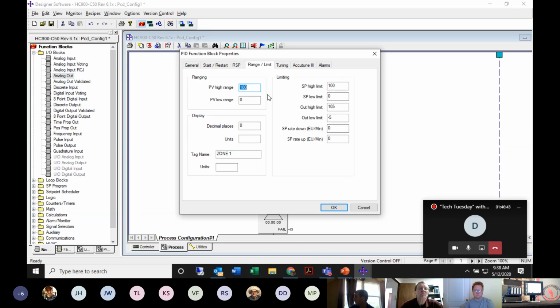Range limits, again, these are the same things you see in a UDC when you program it. You're asked for your PV high range, PV low range, how many decimal points, do I want degrees F or degrees C, what's your set point high and what's your set point low. Do you want the operator only to be able to change the set point to 2000 degrees versus 2400? Output limits, we'll set these to 0 and 100.